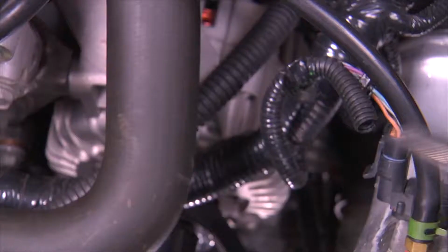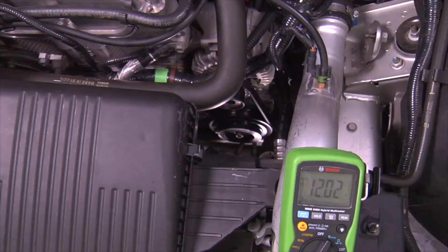In addition to testing the battery, a more thorough voltage drop test must be performed to ensure that the cables and cable connections between the battery, the alternator, and the rest of the charging system are good. If the battery is weak or cannot hold a charge, a good alternator will not properly charge or maintain the state of charge of the battery.